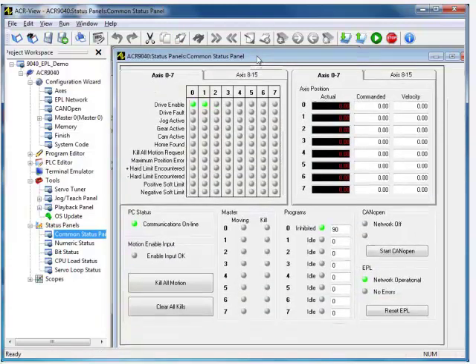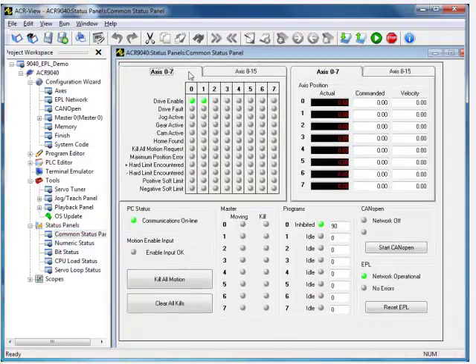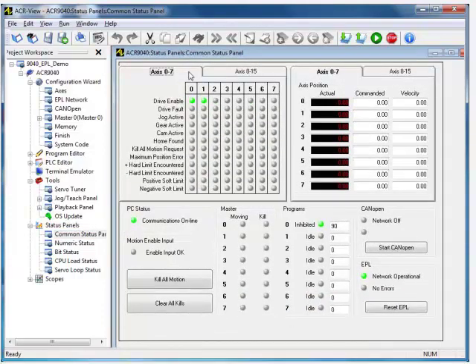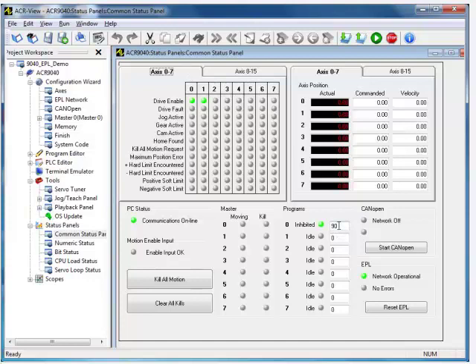Then look in the common status panel. You can see program 0 is running, and it's inhibited on line 90, so if we go ahead and push input number 7, it'll start moving, output 0 turns on, and it stays on the entire time it's moving. And push it again, it runs again. If I hold input number 6 and then push input number 7, it'll run even faster.